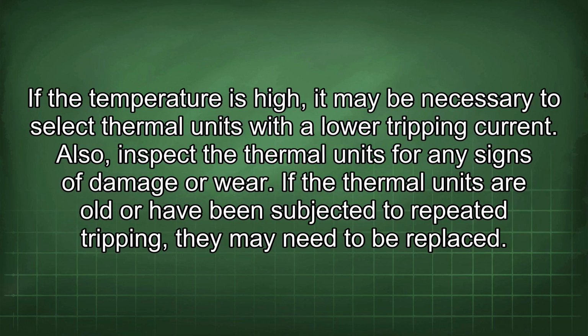If the temperature is high, it may be necessary to select thermal units with a lower tripping current. Also, inspect the thermal units for any signs of damage or wear. If the thermal units are old or have been subjected to repeated tripping, they may need to be replaced.